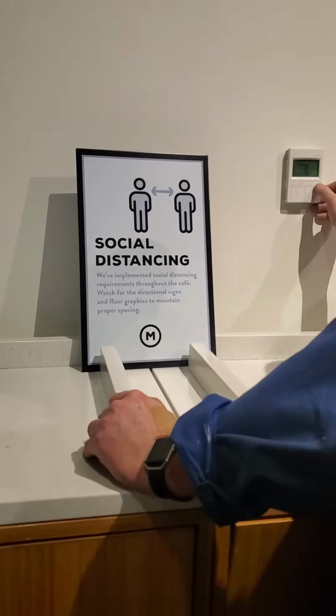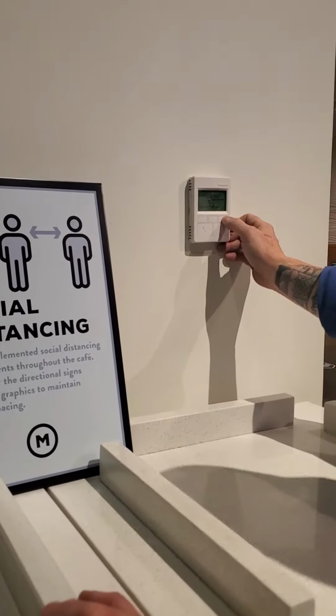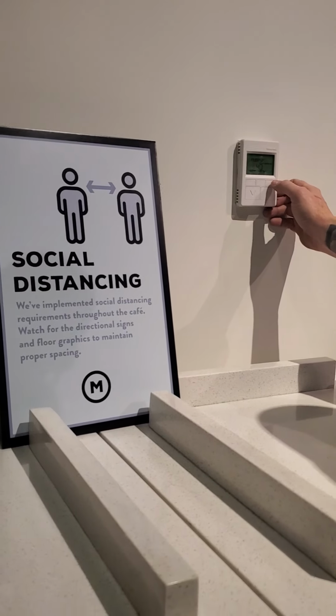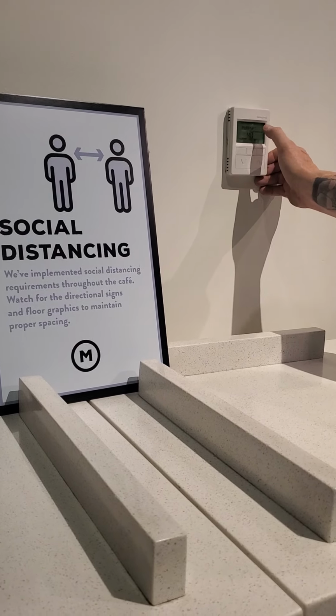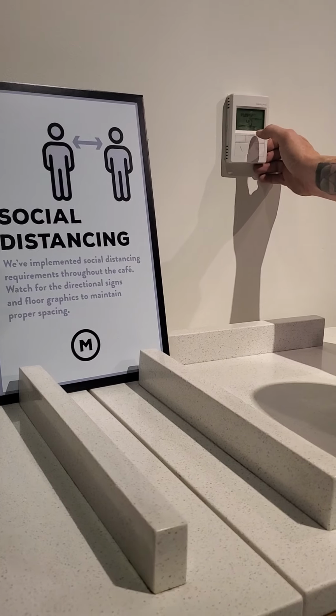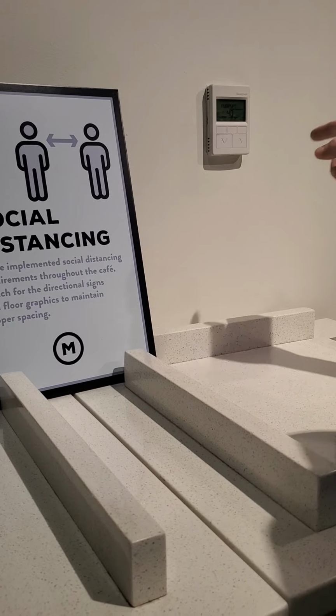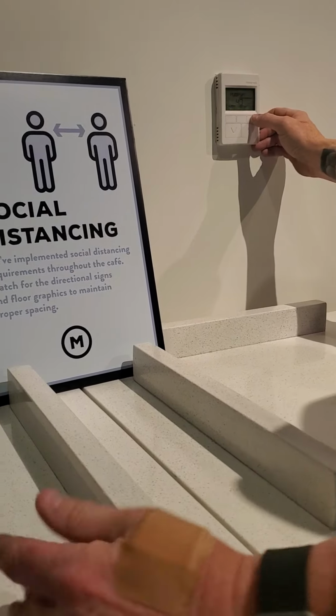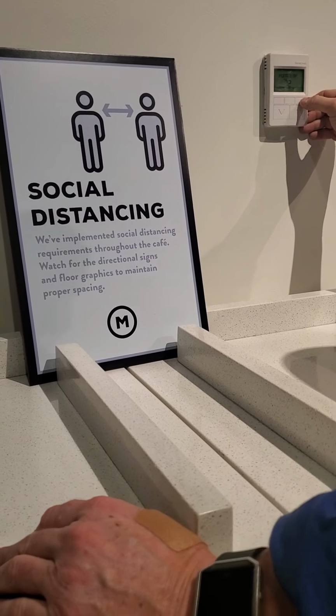There's the room set point, changeover set point 55, and the pump start set point, that's the runaround. When it gets below 40, that runaround is supposed to be running. If it's not, we need to find out why.